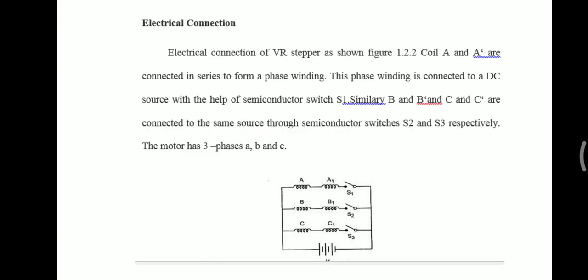When it comes to the electrical connection of the VR stepper motor, coils A and A' are connected in series to form a phase winding. This phase winding is connected to a DC source with the help of semiconductor switch S1. Similarly, B and B', and C and C' are connected to the same source through semiconductor switches S2 and S3 respectively.